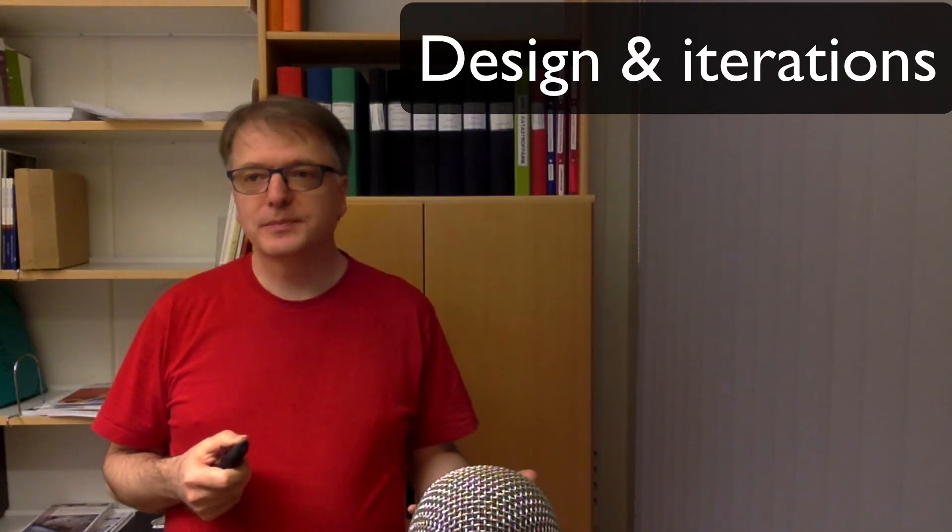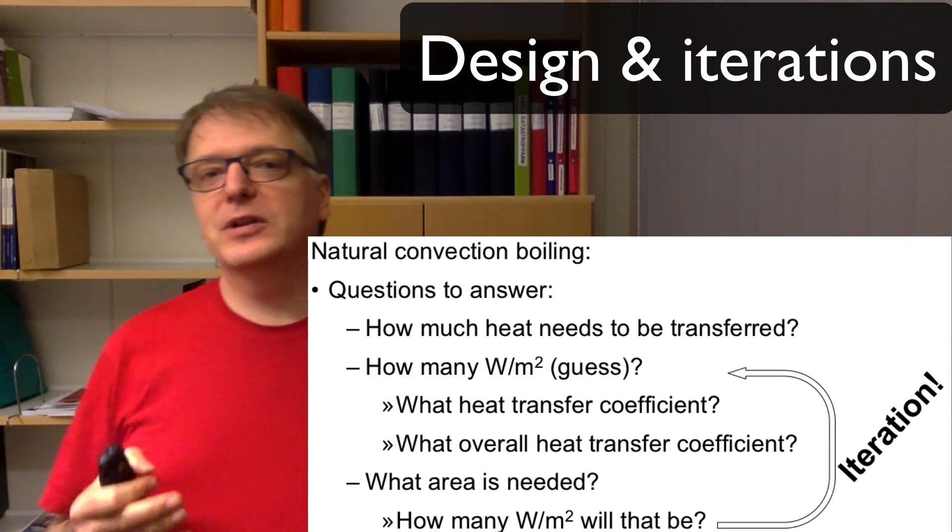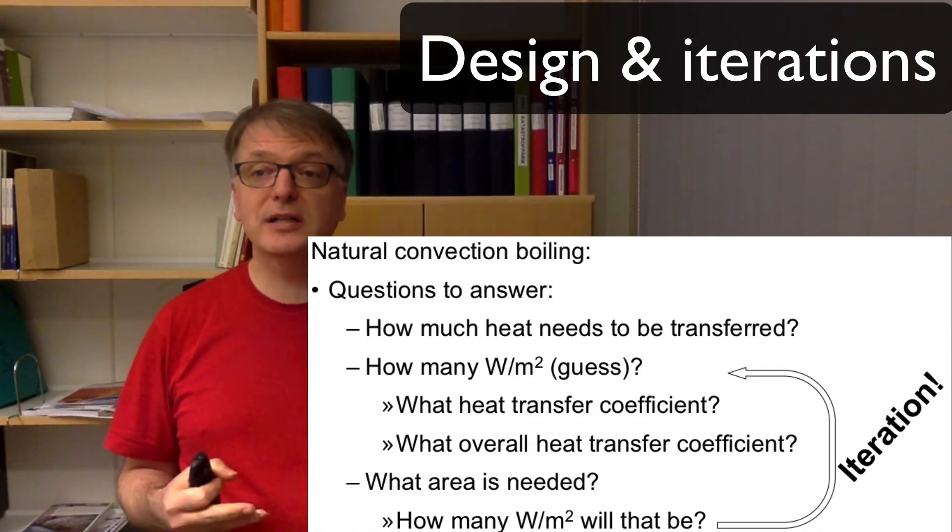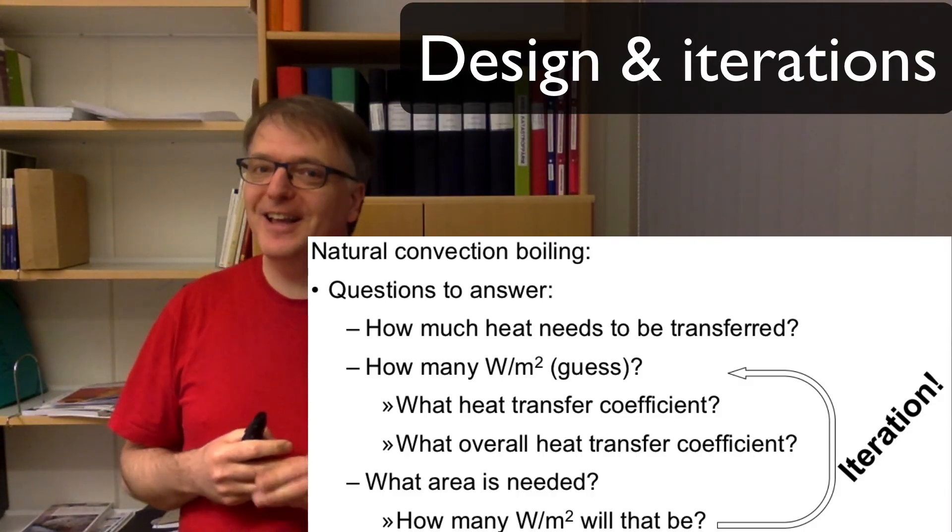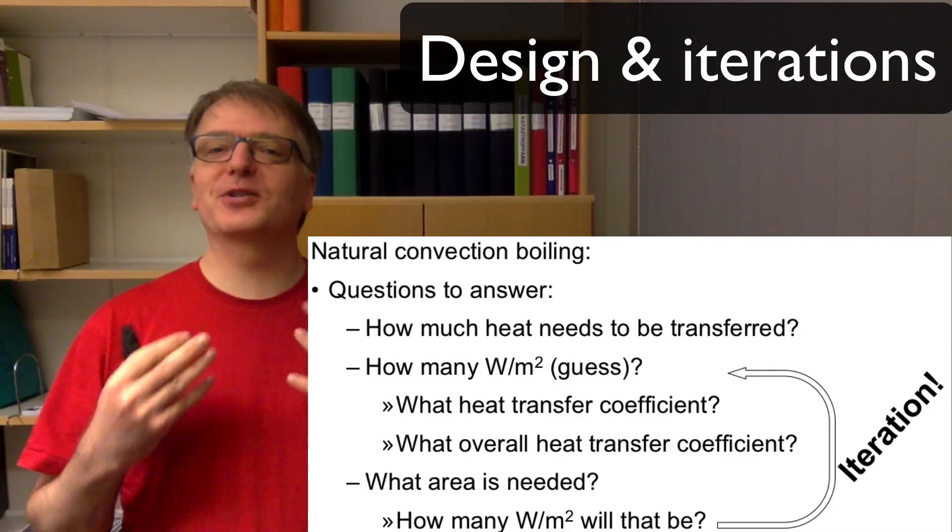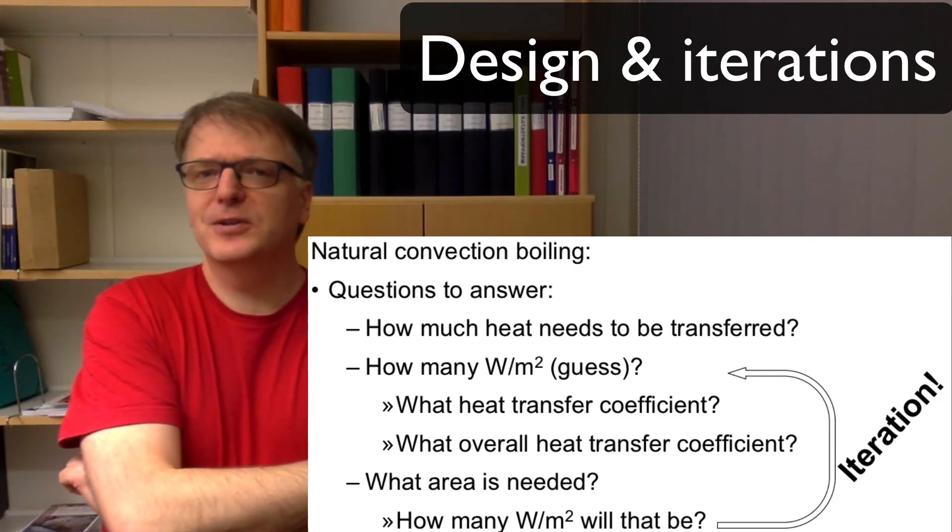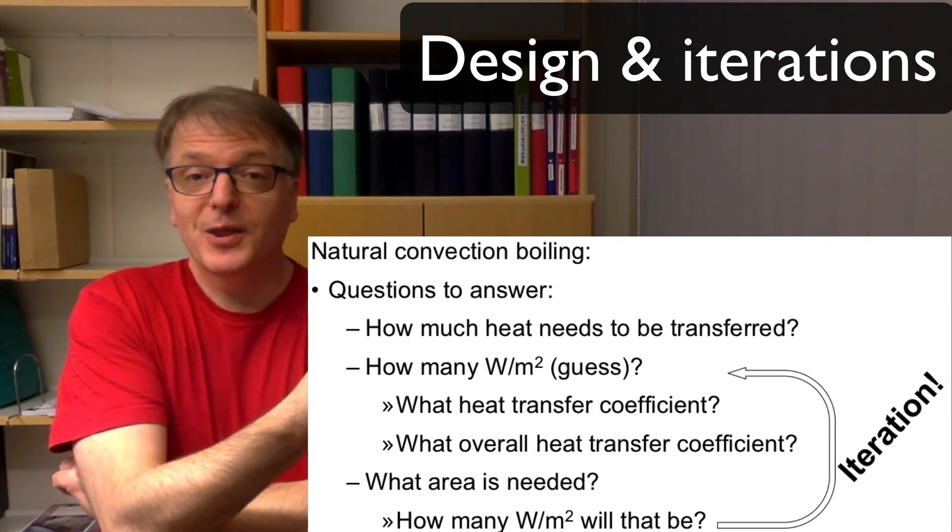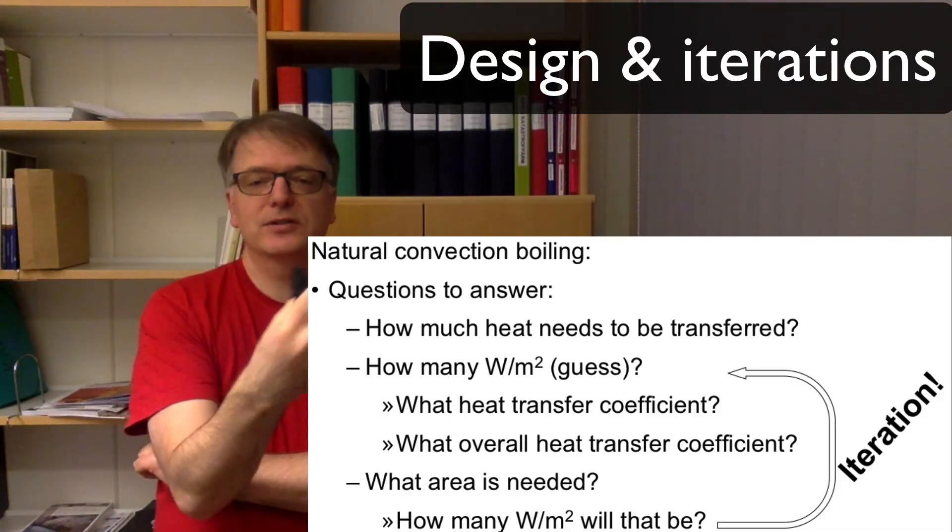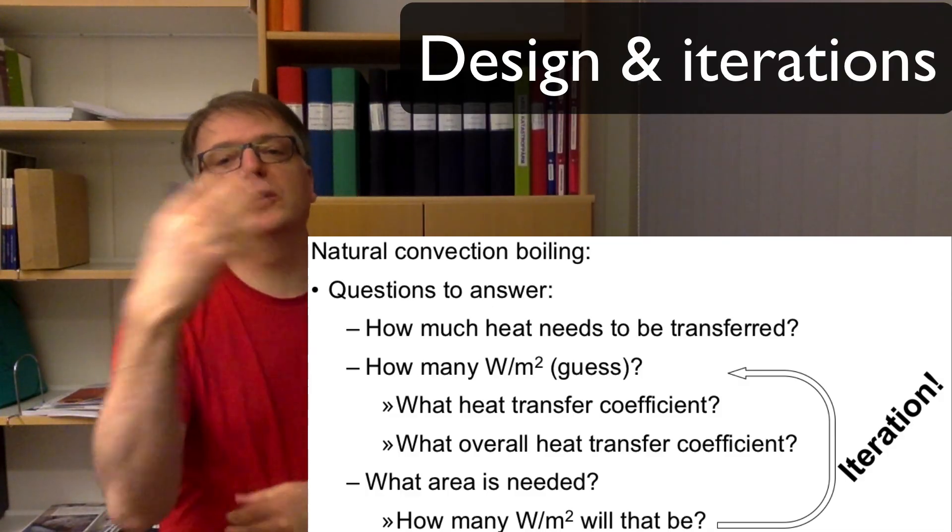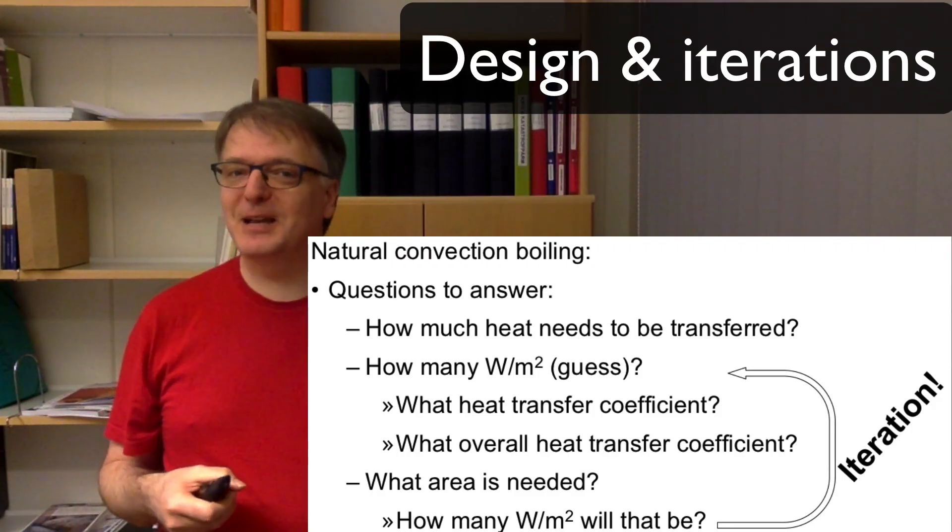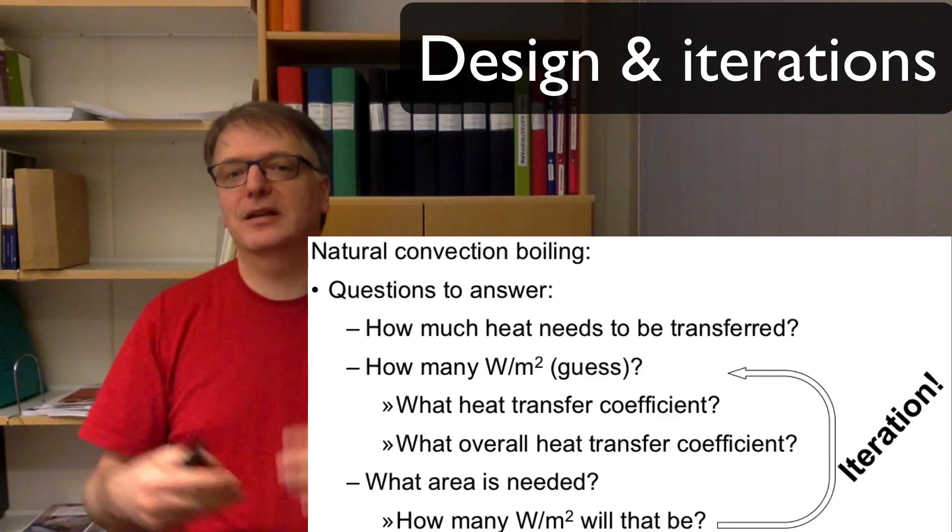If you have boiling, well it all depends on how difficult equations are used. We will use the natural convection boiling. Then the first question we need to ask ourselves is how much heat needs to be transferred, and then the second thing is, okay, so how many watts per square meter will that be? We are going to try to calculate the heat exchanger area and we need to know how much energy is being transferred per square meter. So guess something—you guess how many watts per square meter you need to transfer, and then you calculate the heat transfer coefficients using these equations. Then you calculate the overall heat transfer coefficient, then you calculate the area needed, then you calculate how many watts per square meter will that be. If you're lucky that is the same number as you guessed before, and if you're unlucky you just have to repeat until you find a solution.